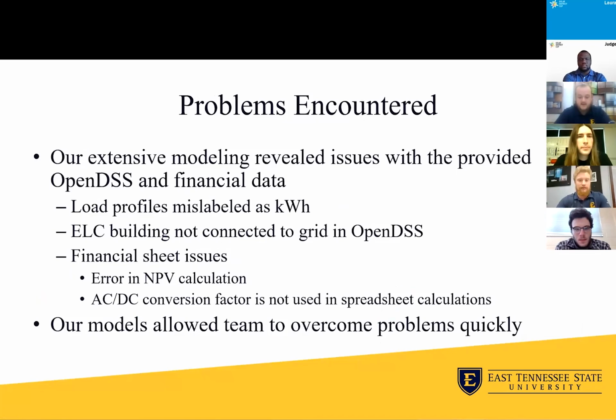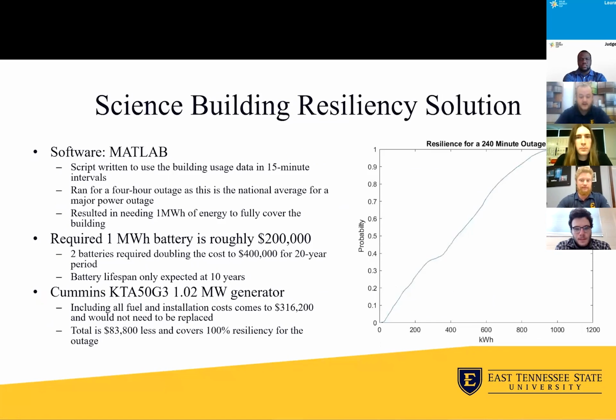The resiliency analysis was conducted using a MATLAB script that took the science building's usage data in 15-minute intervals. The script was run for a total of 4 hours, the national average of a major power outage. This determined that 1 megawatt-hour of energy would be required to cover the building entirely for the 4-hour outage.